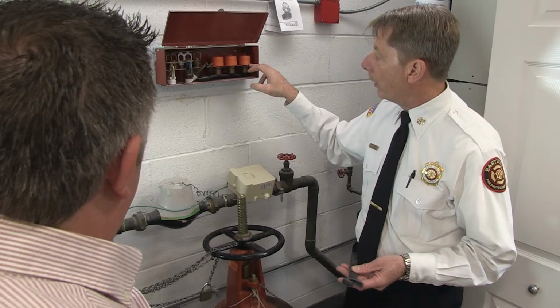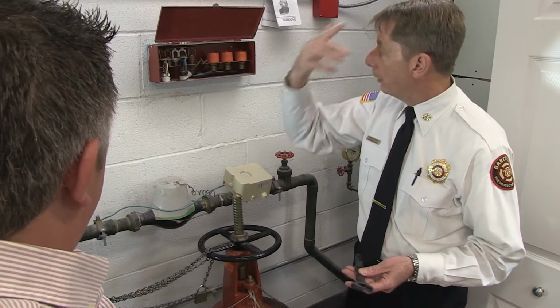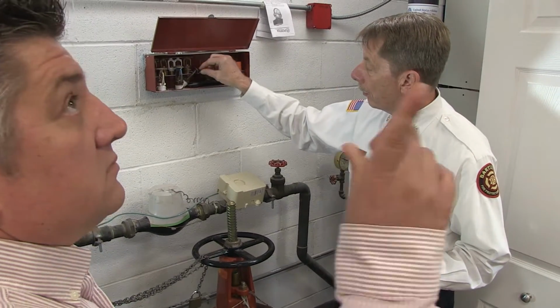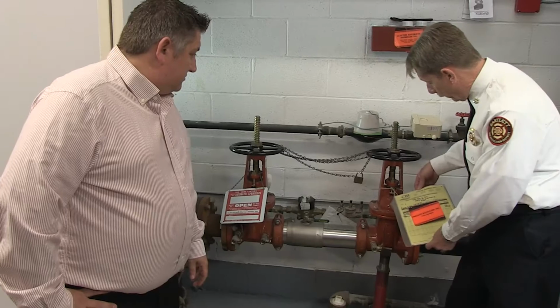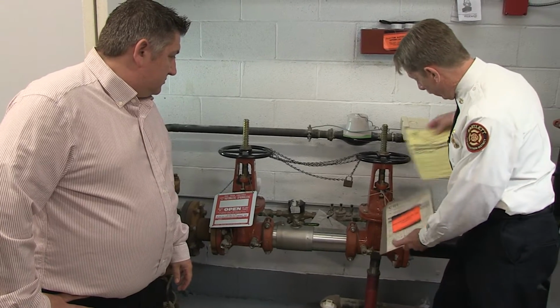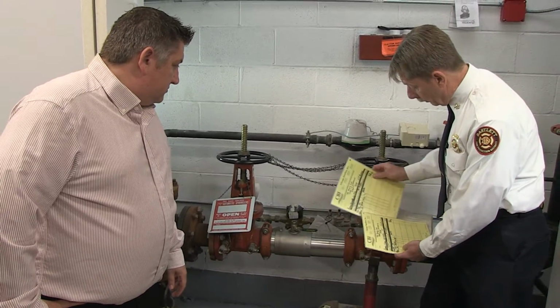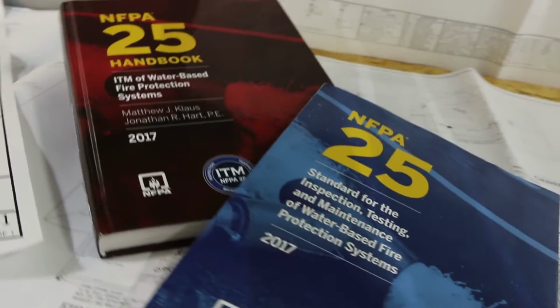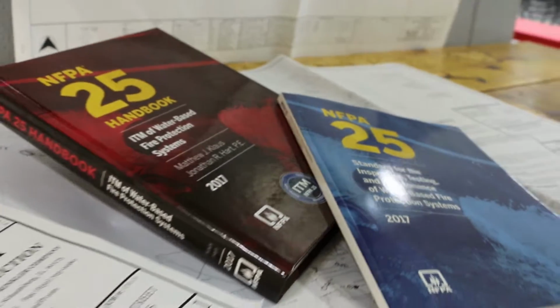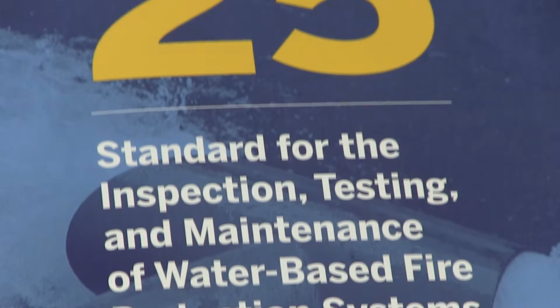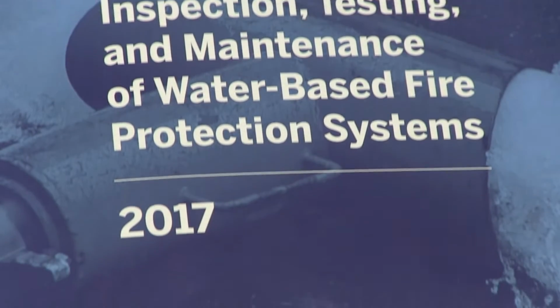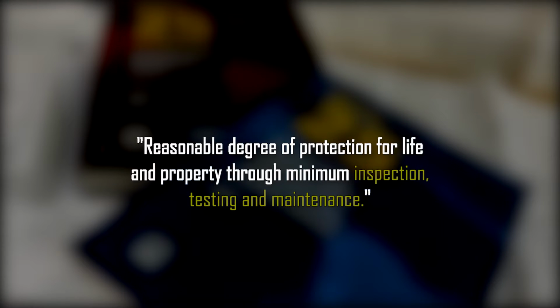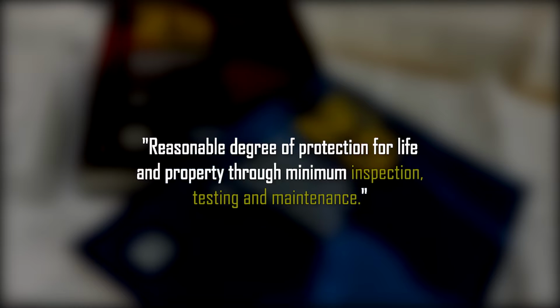However, just like any other system in a building, a fire sprinkler system must be properly inspected, tested, and maintained, otherwise known as ITM, to ensure it works in the event of a fire. So where do you look for information? That's the purpose of NFPA 25. It is the national standard for the inspection, testing, and maintenance of water-based fire protection systems. Compliance with the standard maintains system integrity and avoids failures, ensuring a reasonable degree of protection for life and property.